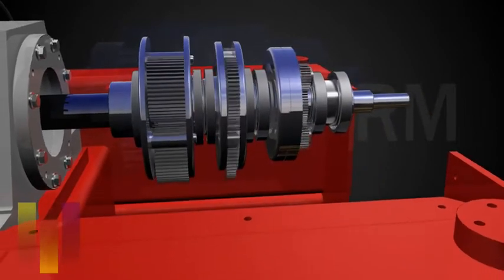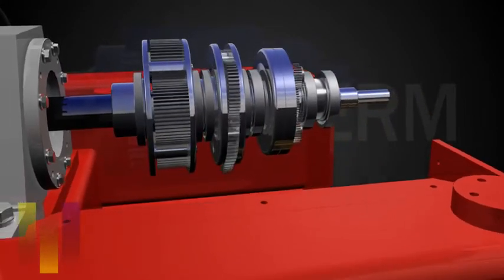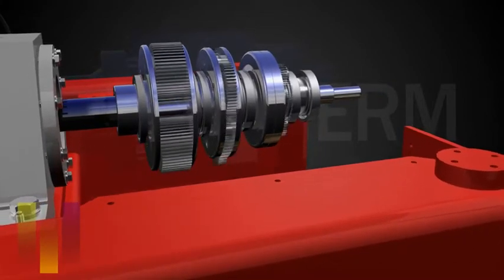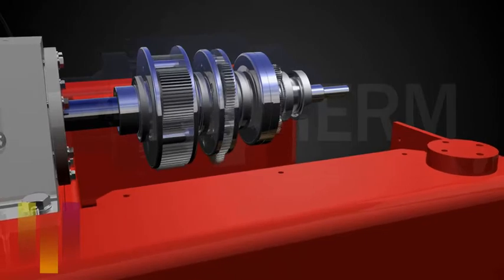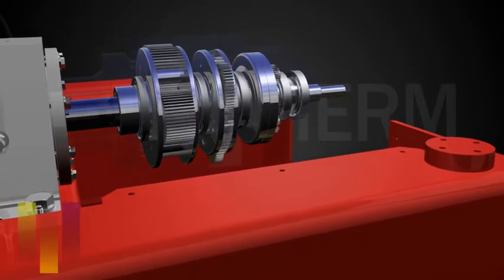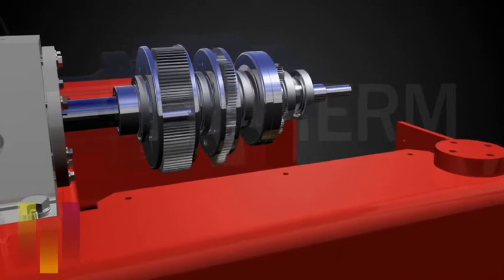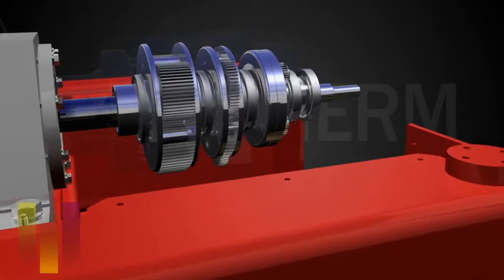Besides the very complex gearbox, this involves V-belts, frequency converters, and additional electrical components. This complicates the controllability of the conveyor drive, which is key for the solid transportation in the bowl. This results in power losses due to the large control chain involving multiple parts.